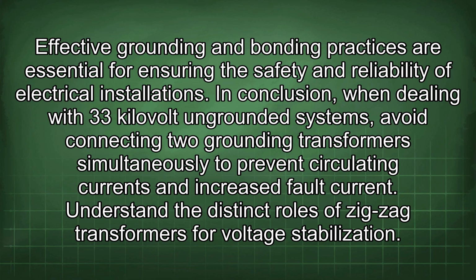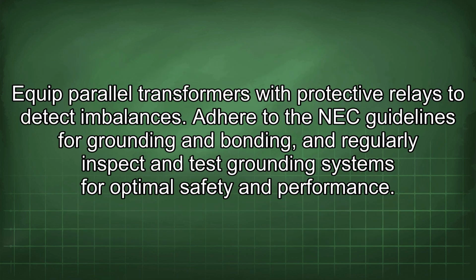In conclusion, when dealing with 33 kV ungrounded systems, avoid connecting two grounding transformers simultaneously to prevent circulating currents and increased fault current. Understand the distinct roles of zig-zag transformers for voltage stabilization. Equip parallel transformers with protective relays to detect imbalances. Adhere to the NEC guidelines for grounding and bonding, and regularly inspect and test grounding systems for optimal safety and performance.